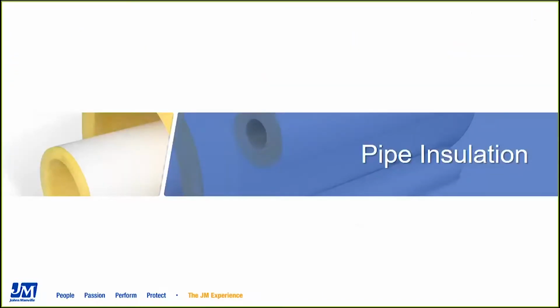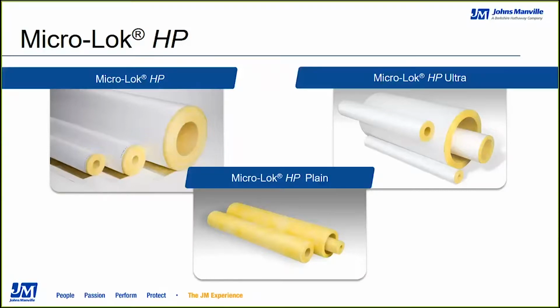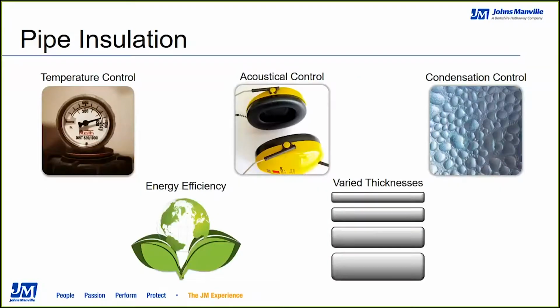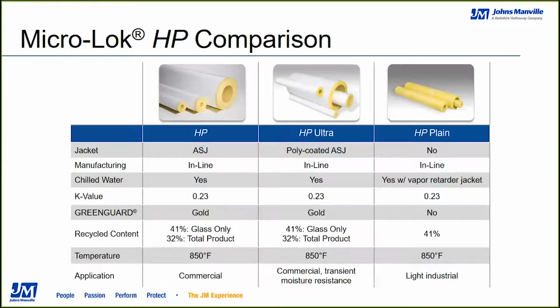Pipe insulation. 3 main product lines in the Micro-Lok category: Micro-Lok HP, Micro-Lok HP Ultra, and Micro-Lok HP Plain. These pipe insulations are used for temperature control, acoustical control, condensation, energy efficiency, and are available in varied thicknesses. Micro-Lok HP is the core of the offering with an ASJ jacket. ASJ is short for All Service Jacket, comprised of paper, a reinforcing scrim, and foil. The product is provided with SSL or self-sealing lap for closure, as well as tape strips to connect pipe sections together.